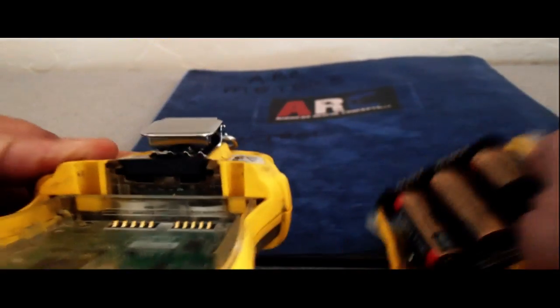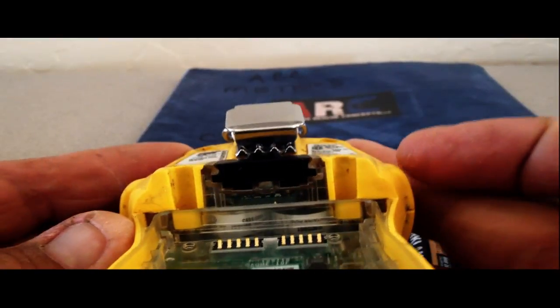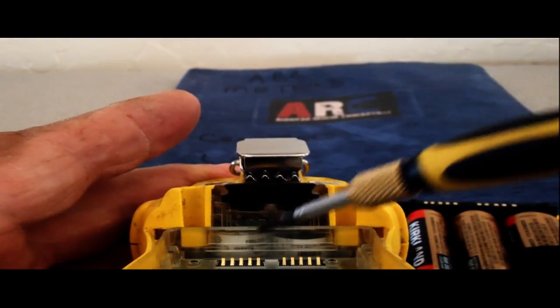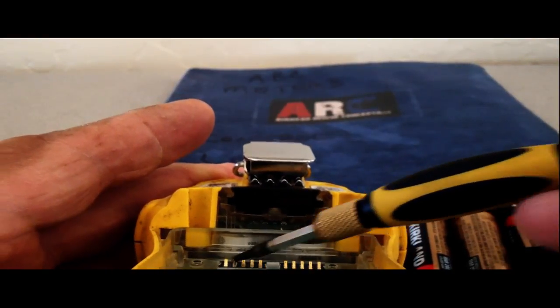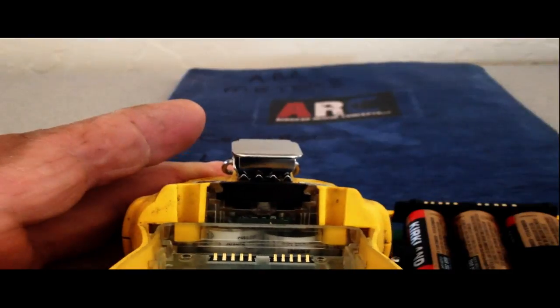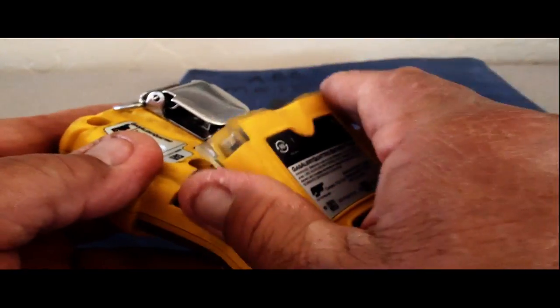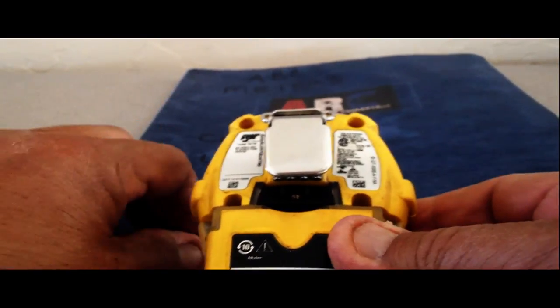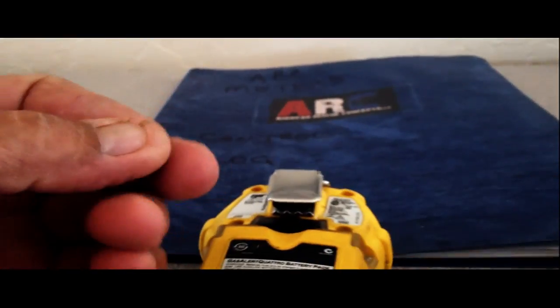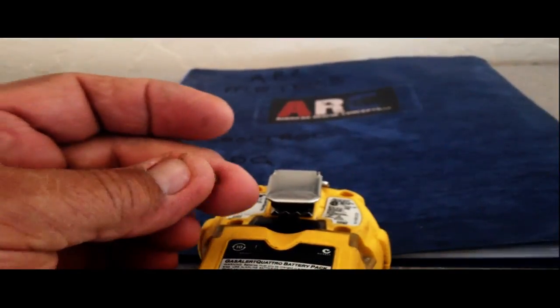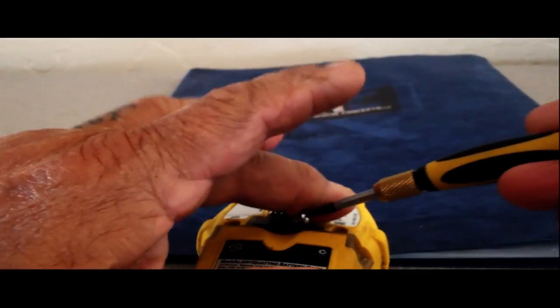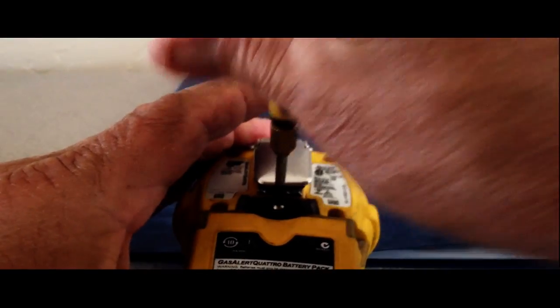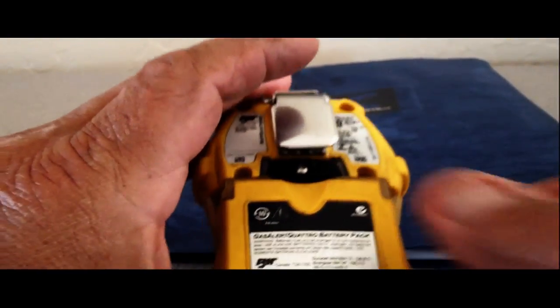back into the unit. By the way, if I hold this up just right, you can see inside here the sensors. It's a different type of sensor in the QUATTRO versus the Max XT2. But there are 4 sensors in there, and those 4 sensors measure oxygen, LEL, H2S, hydrogen sulfide, and carbon monoxide. So I'm going to put that screw back in there to hold it. You saw that tab came down and locked that battery compartment in. So I take my tool and I put my screw back in. Try not to lose those screws, please.